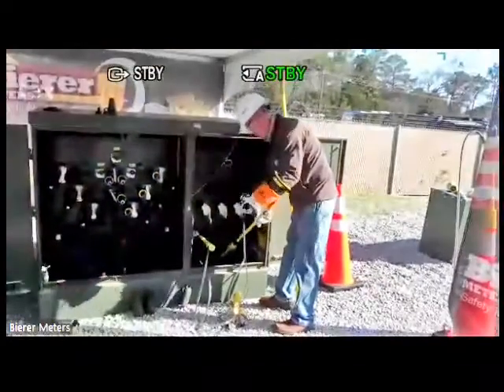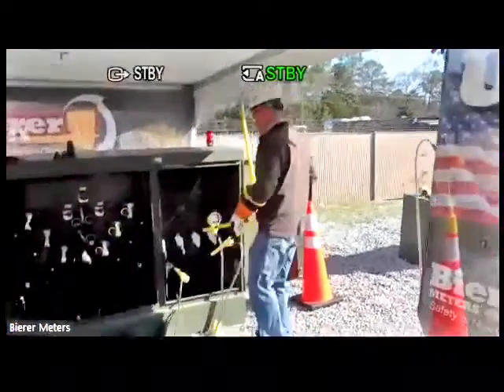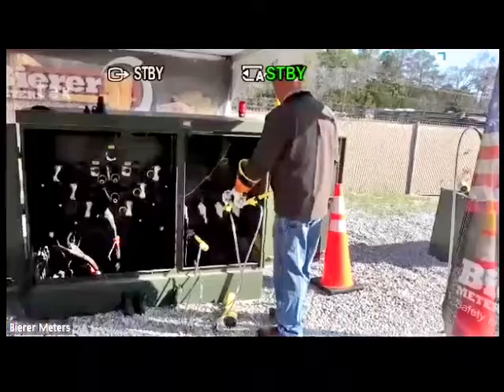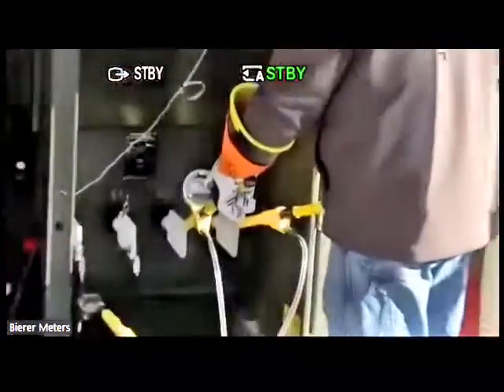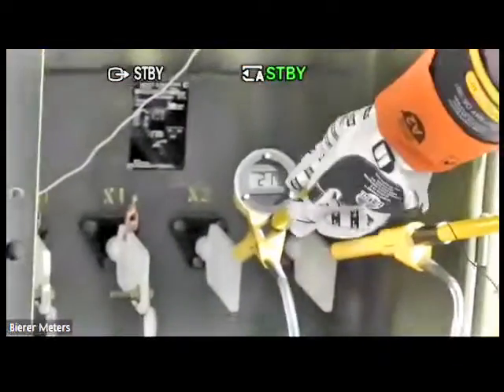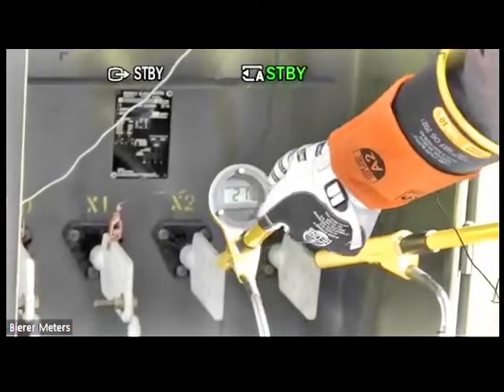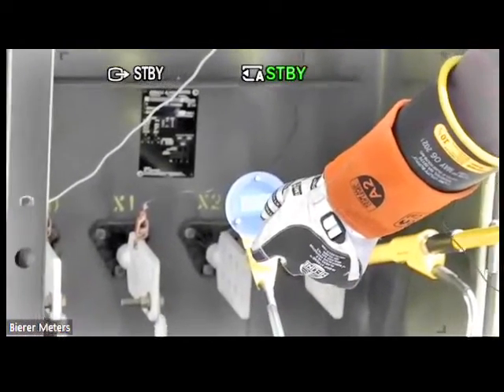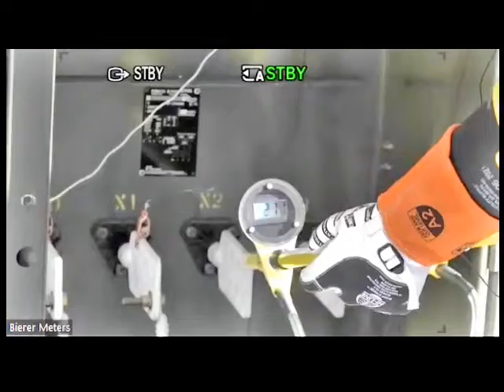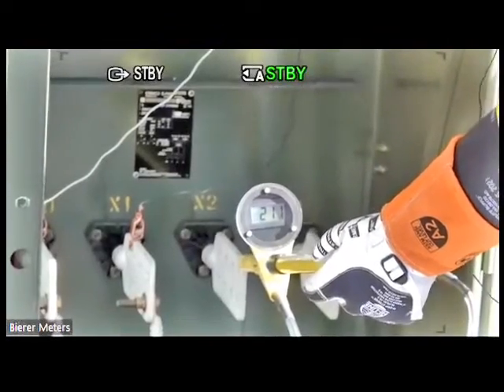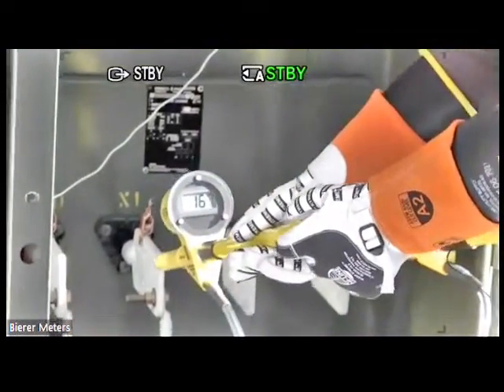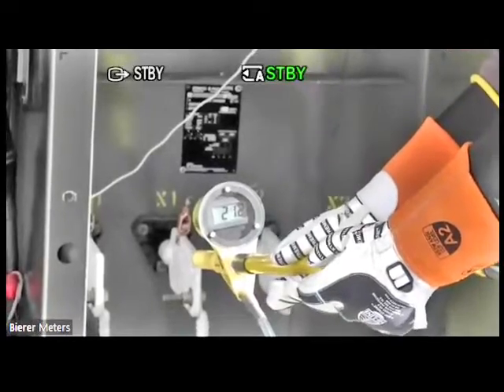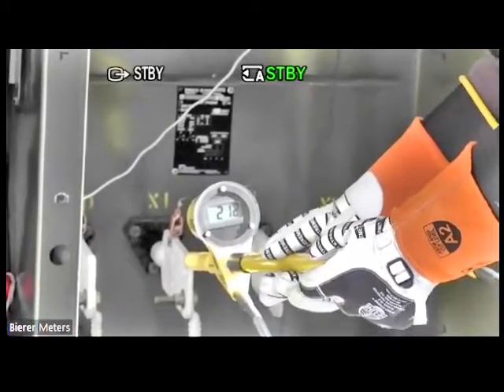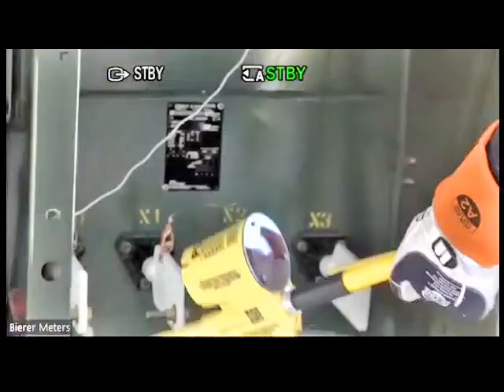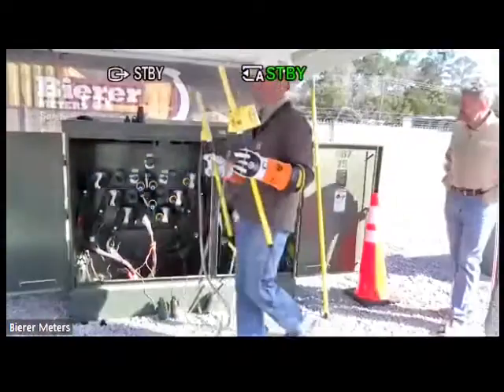Okay. All right. Phase to phase. Take phase to phase readings. Again, you can't phase if one of these is de-energized, so make sure they're all energized. There's my 211 volts. Right there. X1, X3, 211, 212 volts there. So that's my secondary meter there. Secondary phasing, secondary voltage readings.